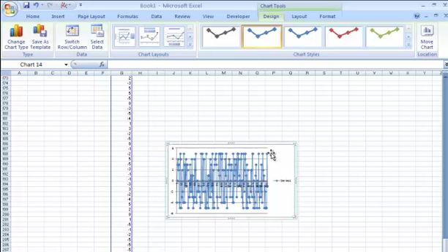Just to summarize, sampling rate is the number of times in a second that the computer records the amplitude of an analog signal. The sampling rate has to be at least 3 times the signal that you're trying to resolve. If you do not have a sampling rate which is fast enough and which is not 3 times the analog signal, the waveforms appear distorted.